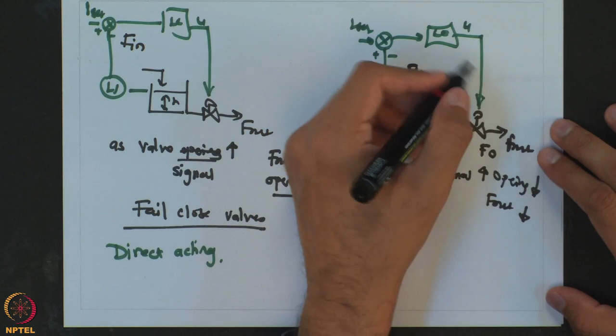But what you now see is, as this is a fail open type of valve, as valve signal increases, the valve opening decreases, or that means F out decreases. That is because when the valve does not have any signal, the valve is completely open, or the valve has 100% opening. So, if that is the case and you try to find out what happens when the height increases, in that case you will realize that in order to increase F out, the controller signal will have to reduce, and because of that, if it is a fail open valve, then the same feedback control system would be reverse acting.